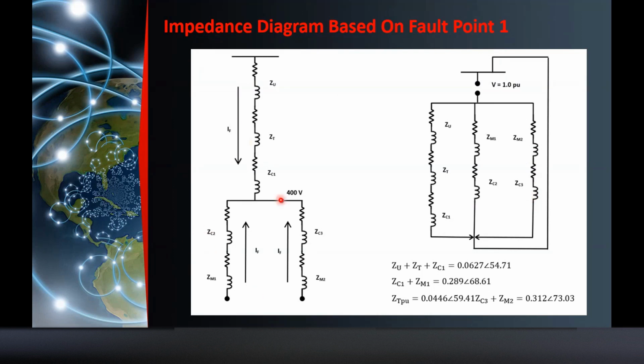So, ZU plus ZT plus ZC1. When you add them, since they are in series, you will get 0.0627 angle 54.7. Say cable 1, sorry, say cable 2 this time. Say cable 2 plus ZM1, you will get 0.289 angle 68.61. Then series again with this, say cable 3.